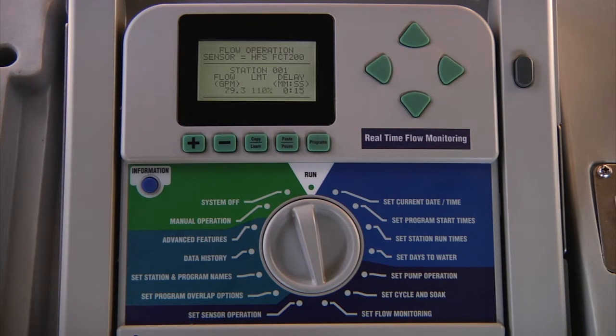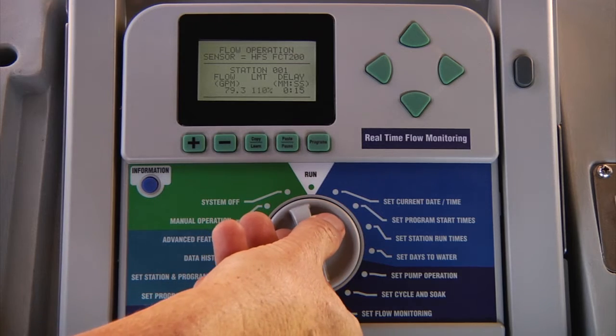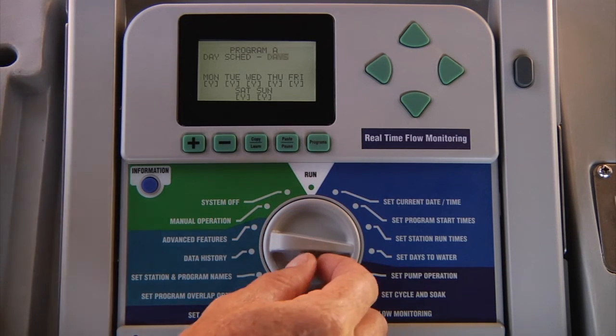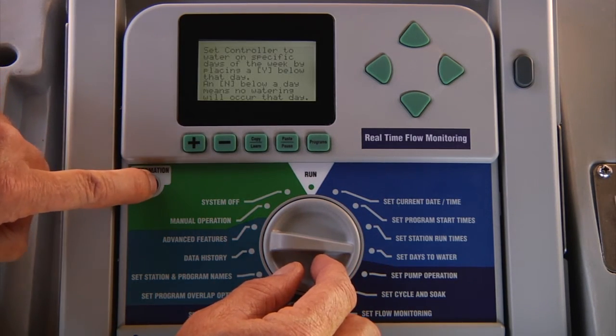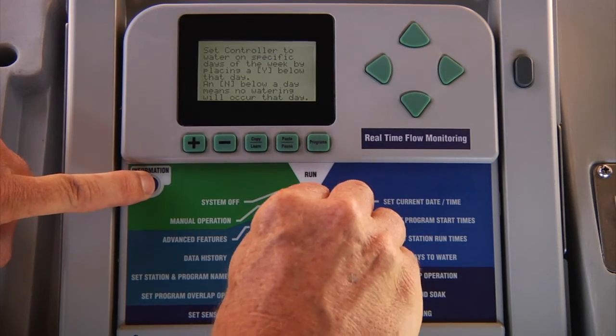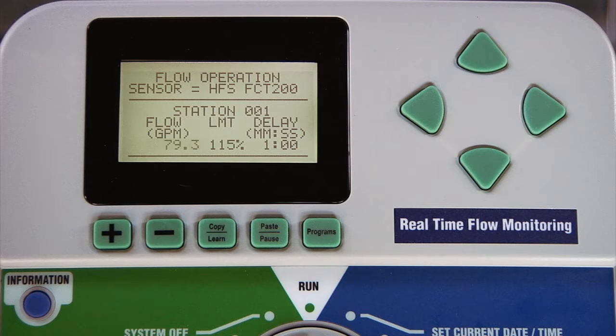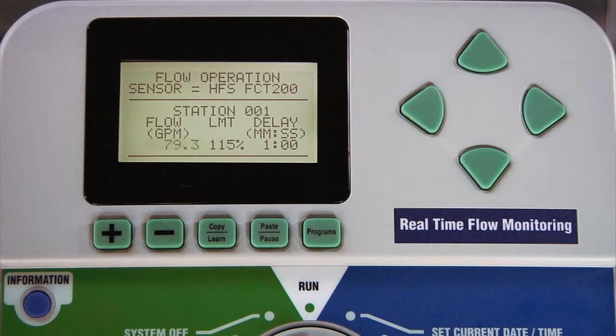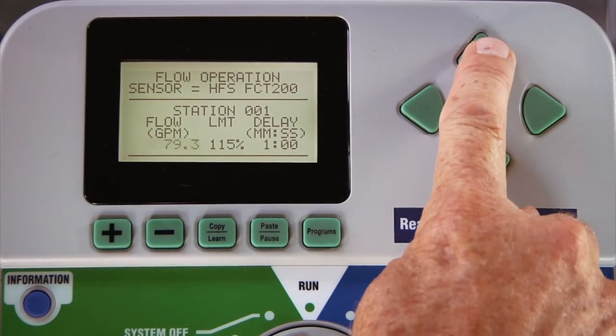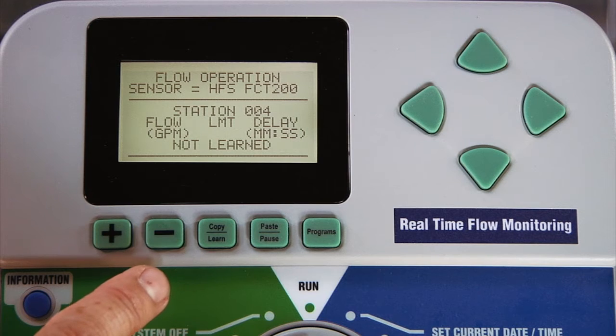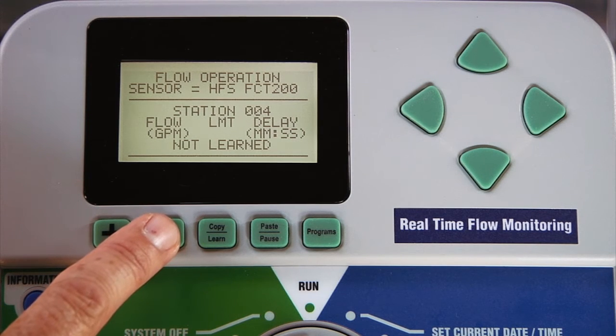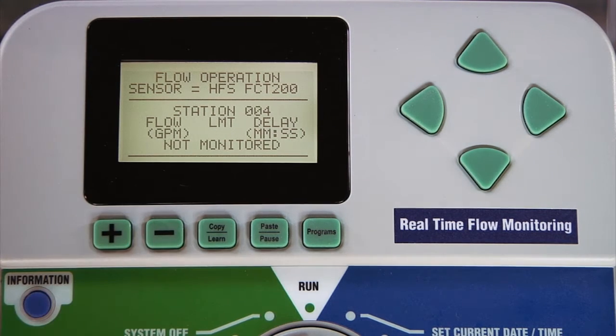To manually enter the station flow or change a station to not monitored, turn the dial away from set flow monitoring, then press and hold the blue information button and turn the dial back to set flow monitoring. Here you will be able to see the learned flow value per station and you'll also be able to edit the station's flow or change from not learned to not monitored. Station 4 shows not learned, so I can change that to not monitored.